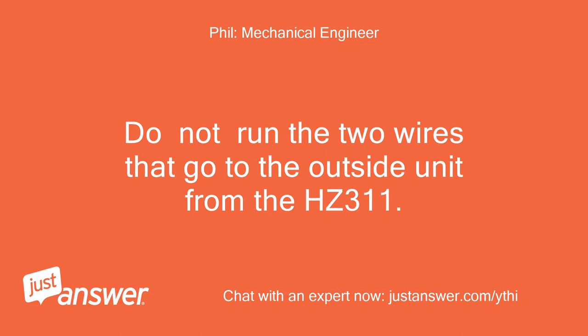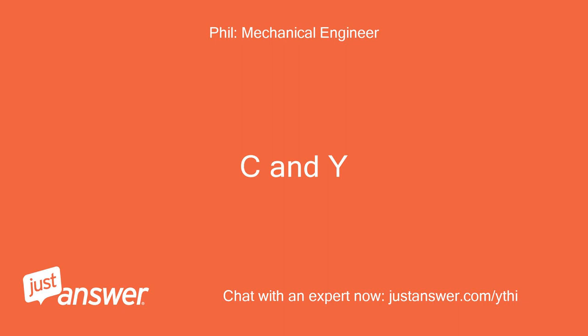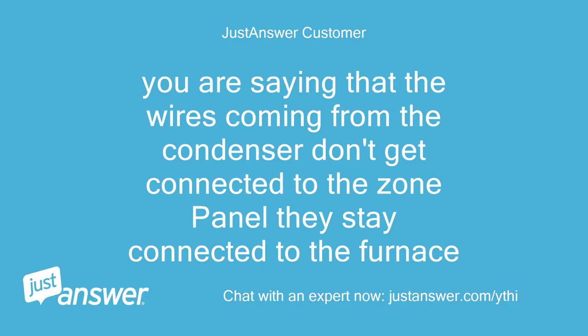Do not run the two wires that go to the outside unit from the HZ311. Run them from the terminal strip in the furnace — C and Y. You are saying that the wires coming from the condenser don't get connected to the zone panel; they stay connected to the furnace.